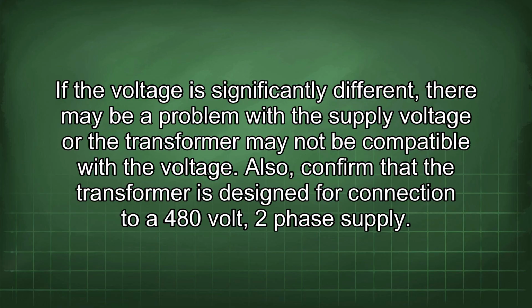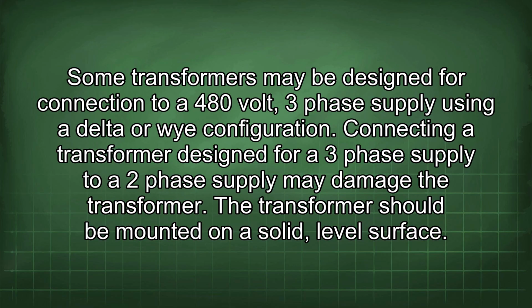Also, confirm that the transformer is designed for connection to a 480-volt two-phase supply. Some transformers may be designed for connection to a 480-volt three-phase supply using a delta or Y configuration. Connecting a transformer designed for a three-phase supply to a two-phase supply may damage the transformer.